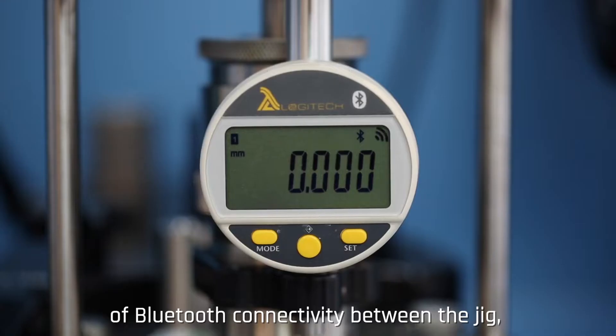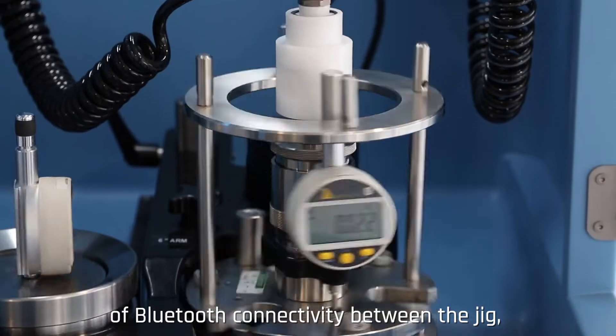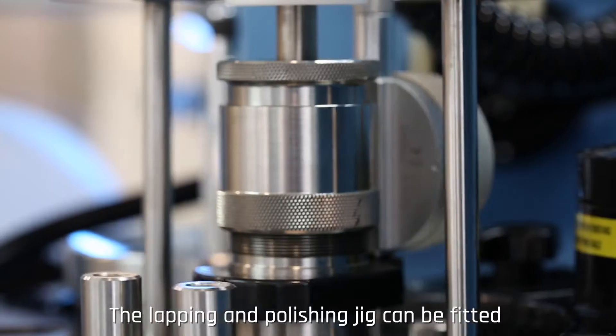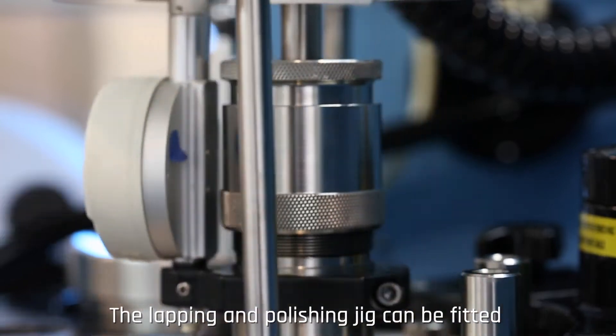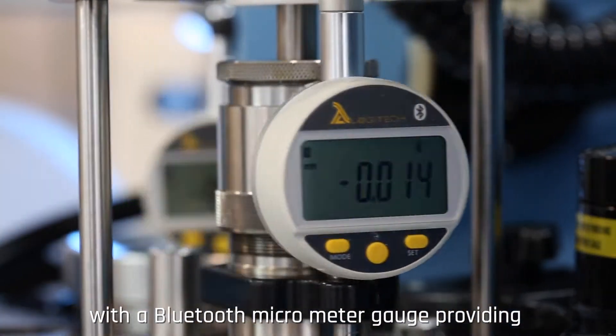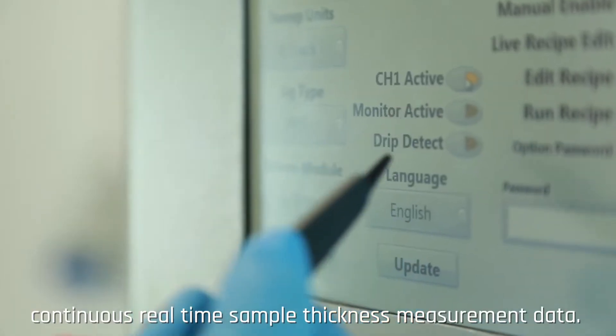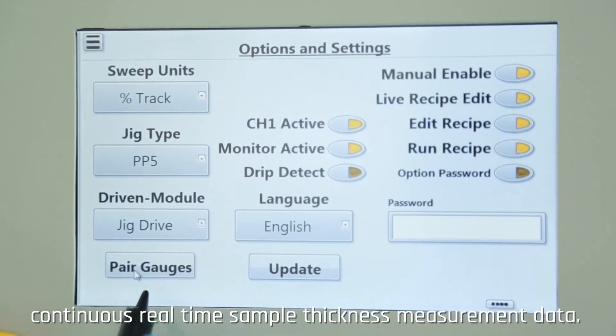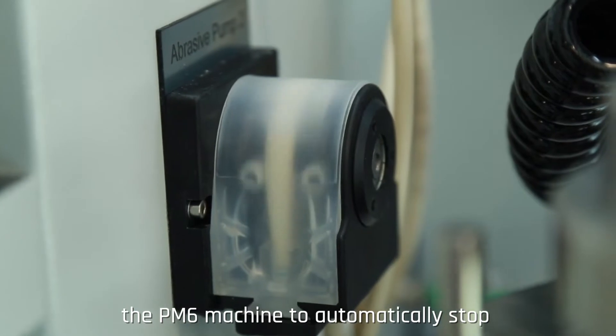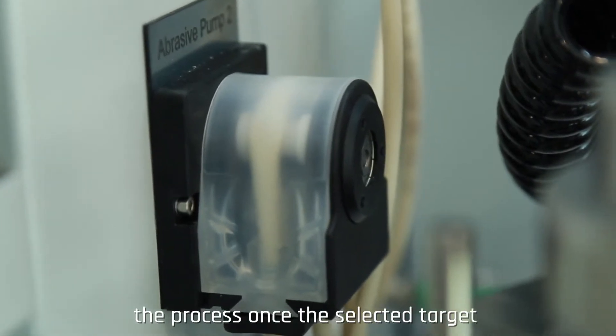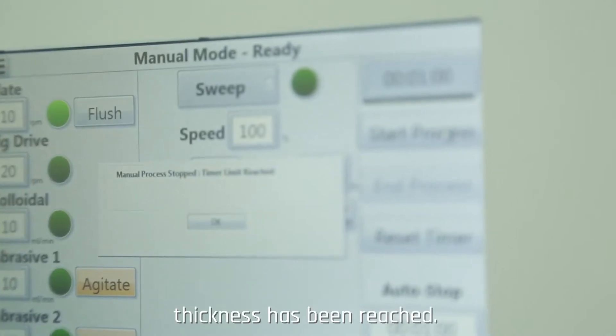The new Logitech PM6 comes with the option of Bluetooth connectivity between the jig, flatness monitor and the graphical user interface. The lapping and polishing jig can be fitted with a Bluetooth micrometer gauge providing continuous real-time sample thickness measurement data. This thickness data can be used by the PM6 machine to automatically stop the process once the selected target thickness has been reached.